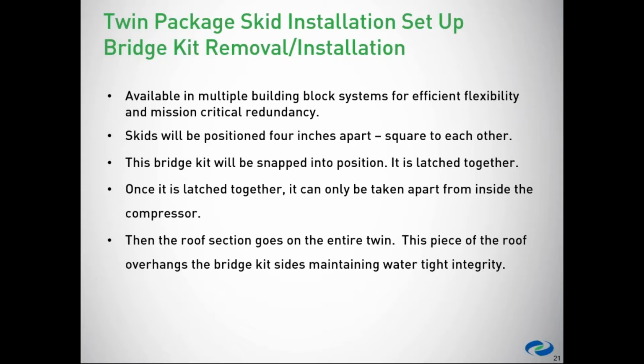They snap into position. The only way to remove these is to actually go through that twin skid access door that gives you access to the compressor from the one side. And basically, there's some latches that you can manually trigger that you can pull this bridging kit off if need be. Once these side pieces are on, the roof section goes on. It would normally be sealed with some kind of a latex sealant, and basically keeps the whole thing watertight.